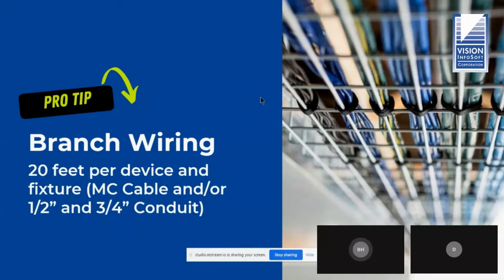So branch wiring, again, a check figure would be to look at the amount of branch wiring, and you should figure probably that your average job will have 20 feet of branch wiring per device and fixture. So you can go back and count up all your receptacles and switches and fixtures. And then you want to see if your total amount of branch wiring, whether you do it in MC cable or in conduit, is typically going to be plus or minus 20 feet per device. If it's way off of that range, then you want to go back and look to see if there's a valid reason for it or if it was just a mistake. So that's one of the check figures you can use.